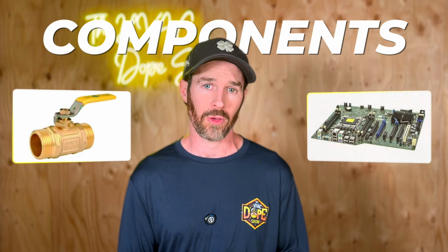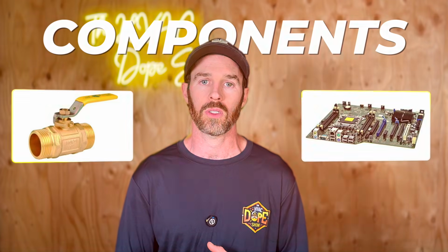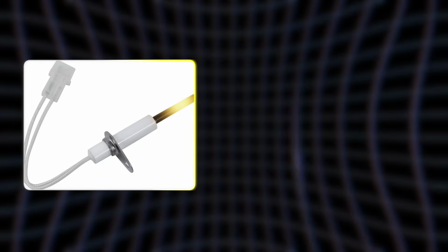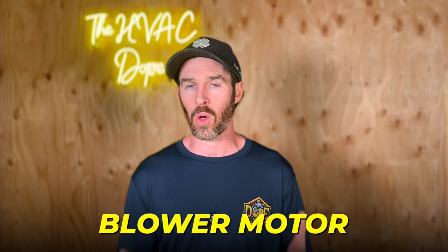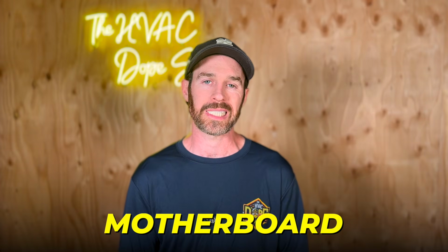The same thing is true for components like gas valves or motherboards or other components on the system that tend to fail. Other items that are normal wear and tear items like hot surface igniters or flame sensors, are not as big of a concern, because those are also cheaper repairs than a blower motor or a motherboard replacement. But the bottom line is that's the gist of why you would really strongly want to consider replacing a system once it has a cracked heat exchanger.